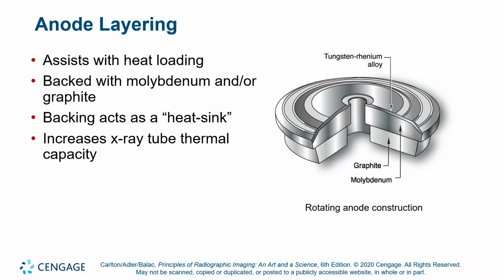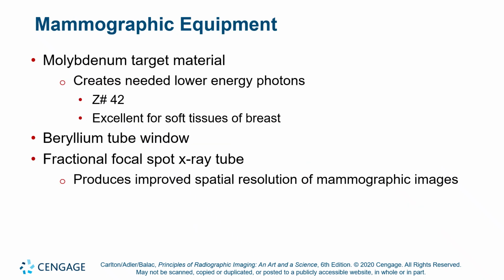Okay, and all this is the diameter of the anode roughly, but effectively the anode's mass determines its heat capacity. It's a primary factor in determining the heat capacity of the X-ray tube. A 6-inch anode versus a 12-inch anode: if everything else is the same, the 12-inch anode is going to have double the heat capacity of the 6-inch anode.